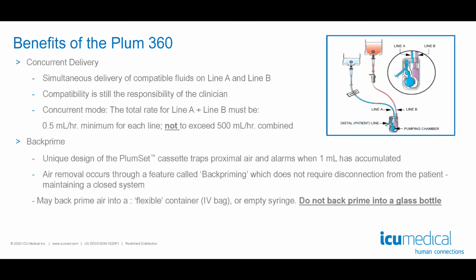Additionally, this pump also allows for concurrent delivery, a new feature we do not currently have with Alaris. Concurrent delivery is a function that allows both channels A and B to run at the same time. This can be useful for specific clinical situations with specific medications, for example, a septic patient that needs continuous IV fluids and IV antibiotics with no concern for fluid overload. You must always check for compatibility prior to running any medications concurrently. However, there are certain medications that we would not want to use concurrent delivery for, like our high alert medications.